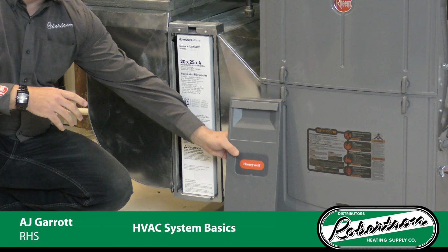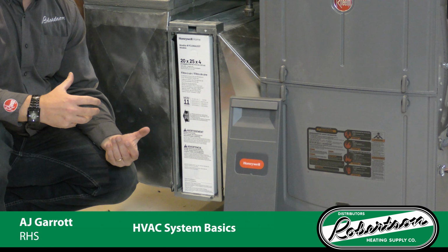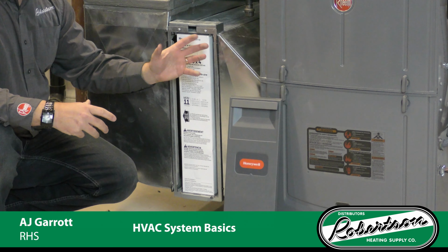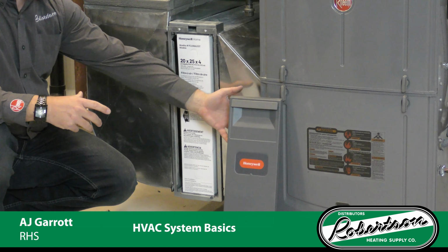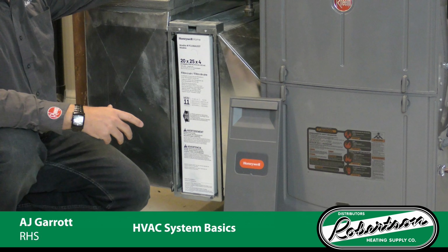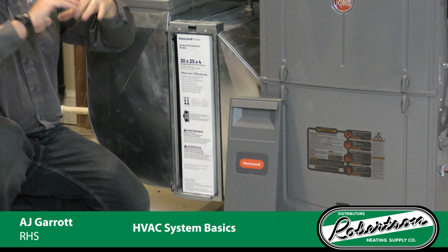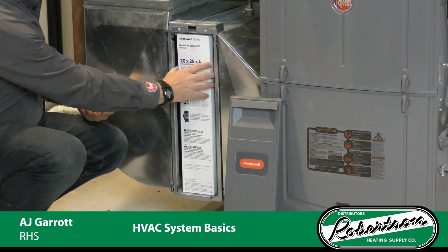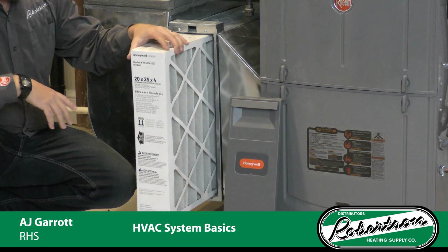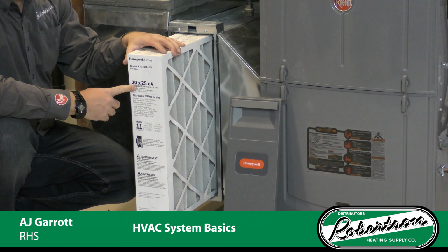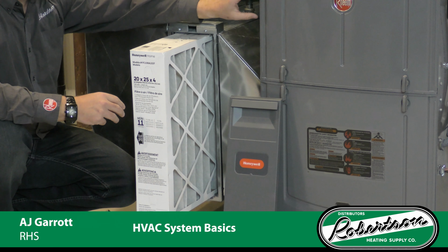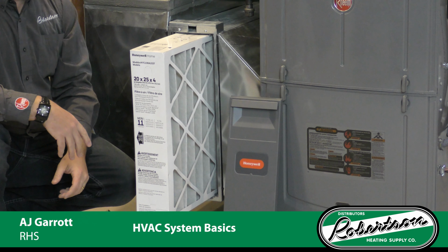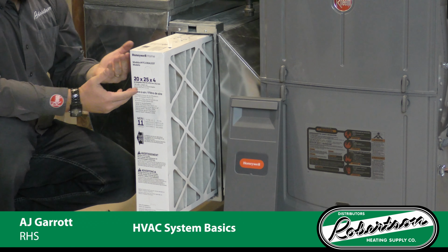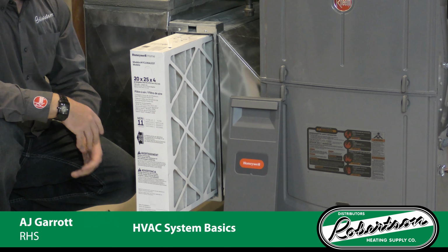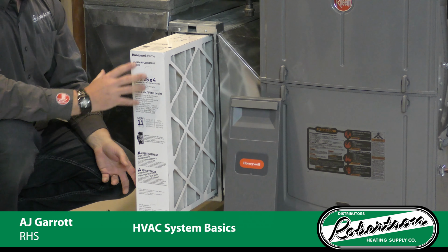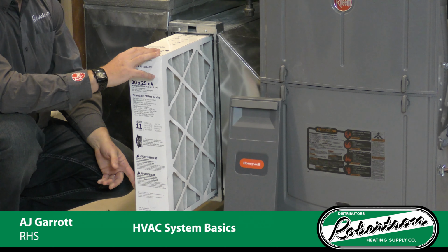The filter is very, very important in a system to keep any kind of dust particles or any other large particles from coming across the furnace blower and being stuck into the coil and even distributed out to the air that you're breathing. This media filter here is a 20 by 25. It is the proper size for this application. You're going to find some media filters are 16 by 25, 20 by 25, or even 20 by 20 are very popular sizes for these types of filters.